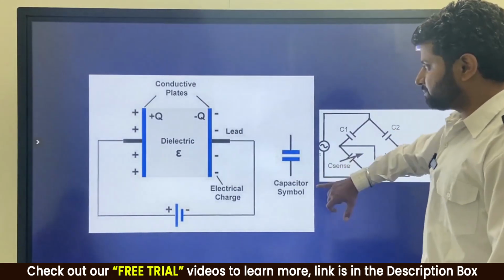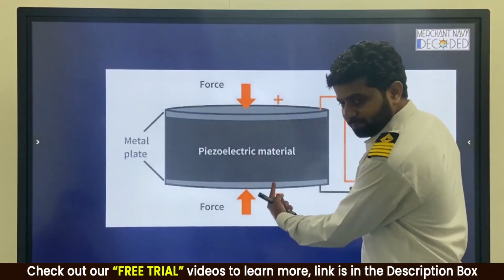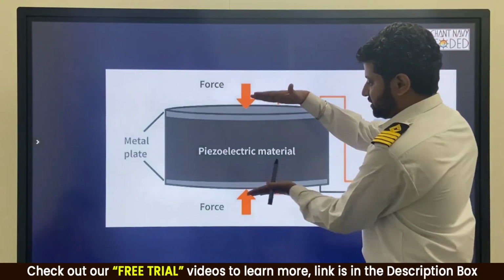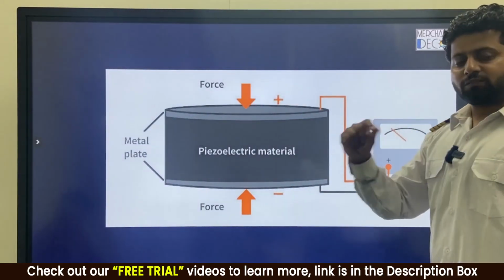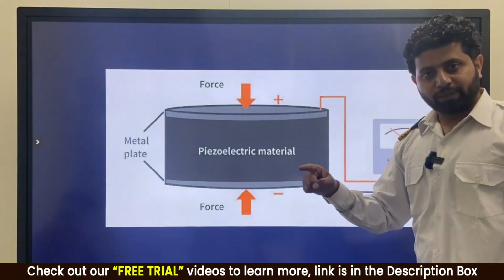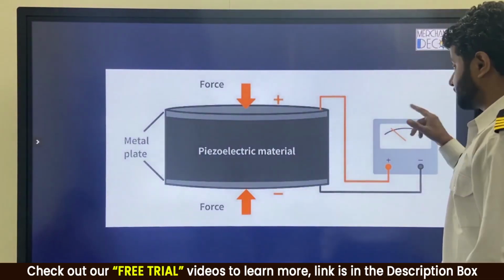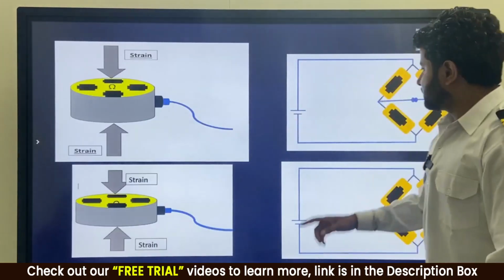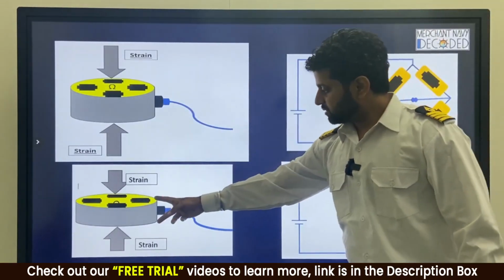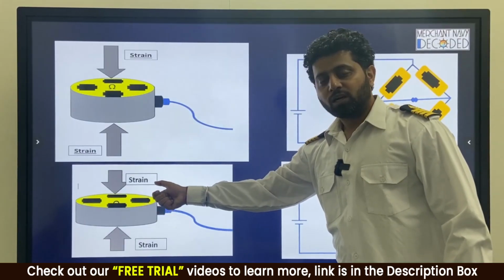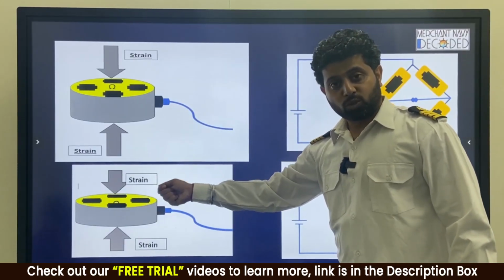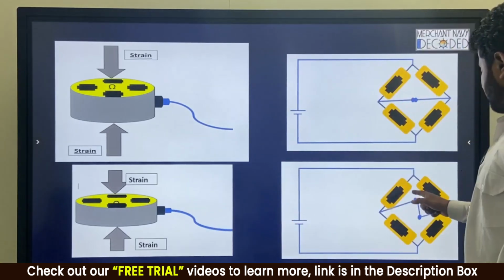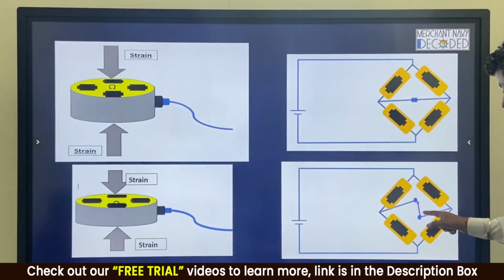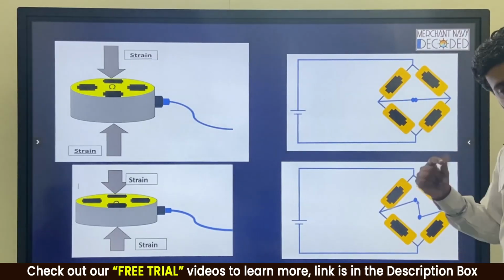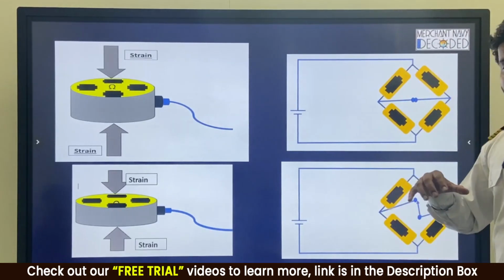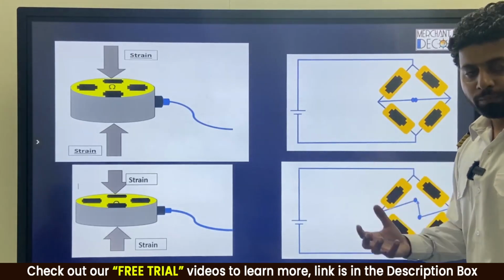So once again repeating, even over here, if there is a force applied, that is pressure applied, pressure into area is force, this piezoelectric material will generate voltage, we convert it into a standardized instrumentation signal, and we get an answer ki bhaiya how much is the pressure. Out here, in case of strain gauge, this is a balanced Wheatstone bridge, strain acts, the shape changes, resistance changes, because R is equal to rho L by A, the length has changed, the area has changed, it becomes an unbalanced Wheatstone bridge, due to which the current starts flowing over here, and when you measure this current, Jai Mata Di. Again, this current can be converted into a standardized instrumentation signal of 4 to 20 milliamps, and then we get an answer.